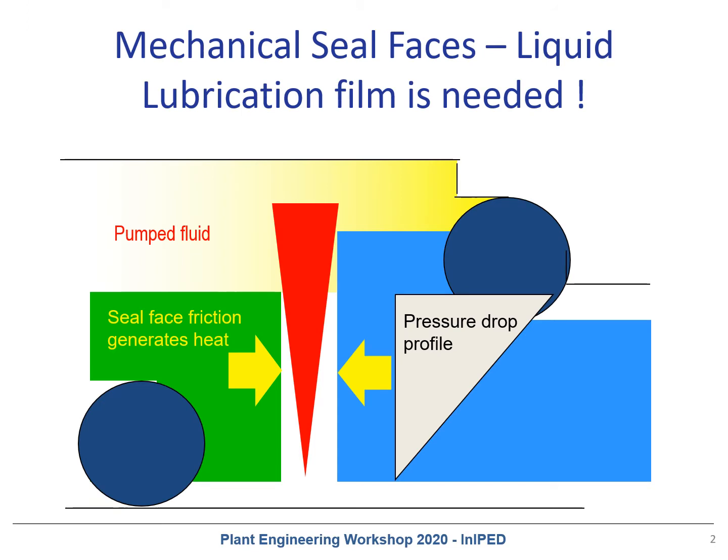Mechanical seals consist of two seal faces sliding on each other, shown here in green and blue. The pump fluid itself provides the required liquid lubrication, shown here in red. Seal face friction generates heat, and as pressure drops in the sealing gap, light hydrocarbons with low vapor pressure margins start to vaporize.